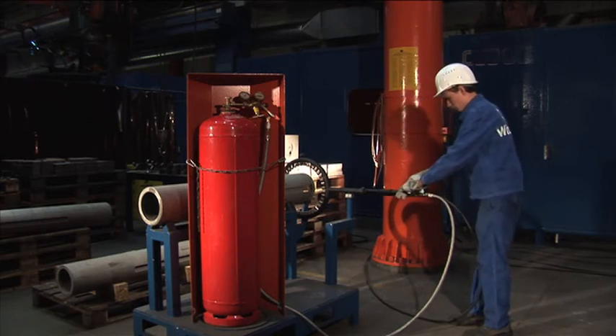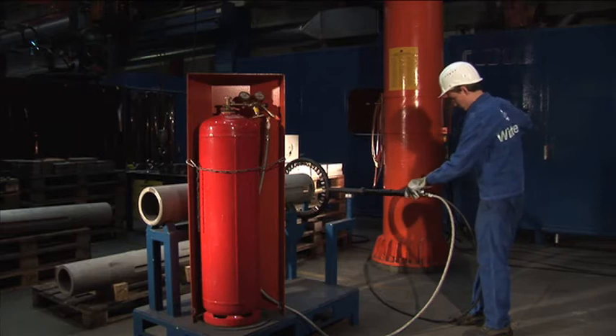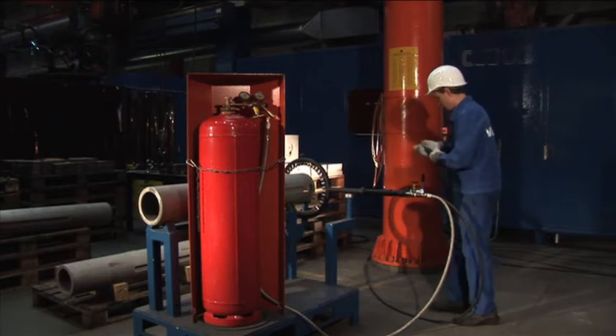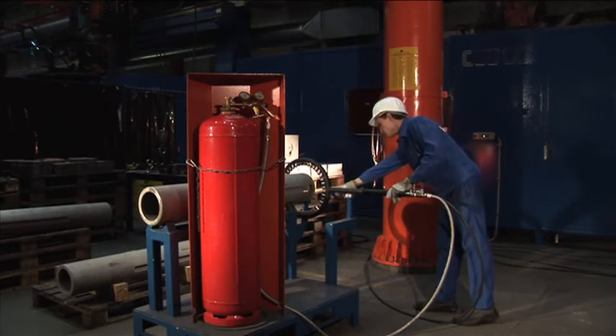With the EcoVen, up to three-quarters of the required combustion air is taken from the ambient atmosphere. Therefore the expensive compressed air requirement is reduced by up to seventy-five percent.